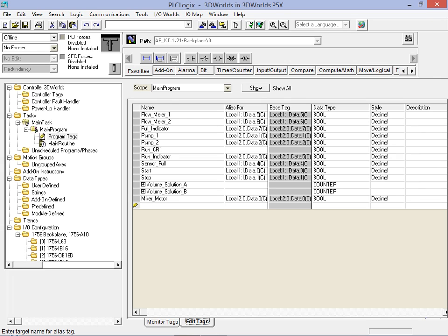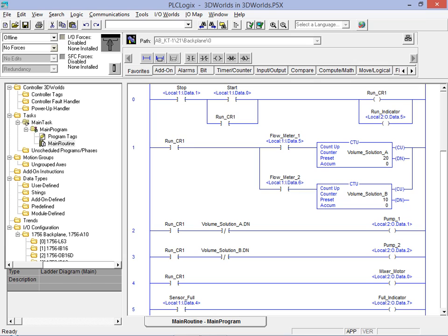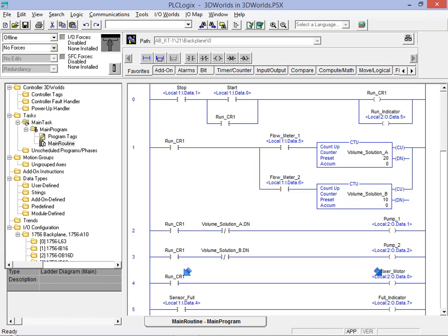Rung 4 consisting of a normally open contact and an OTE instruction has now been added to the program. We have assigned our new tag to the OTE instruction and this output would control the mixing motor. Note that the motor will be active as soon as the seal in rung has been locked up. This should engage the mixing motor once the start button is pressed.